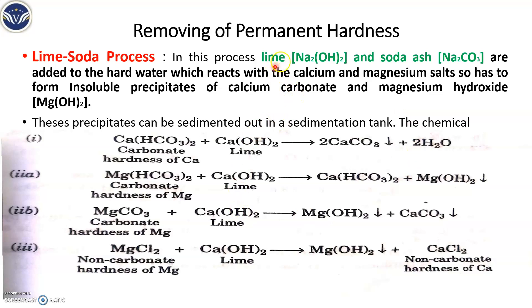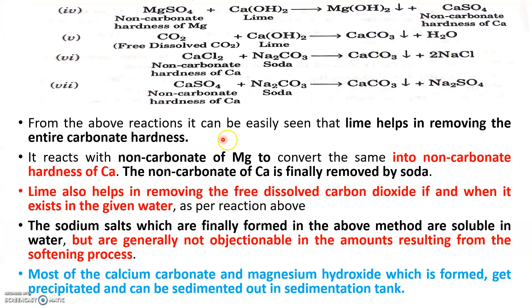So we are adding lime and soda ash here. By adding that, what happens is there is a chemical reaction taking place with calcium and magnesium salts. These get precipitated as calcium carbonates and magnesium carbonates, as you can see in the sedimentation tank itself and in the following reactions.